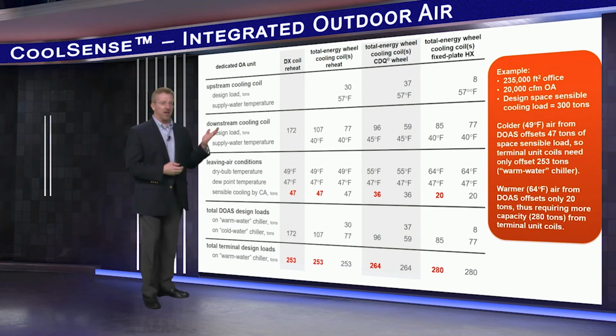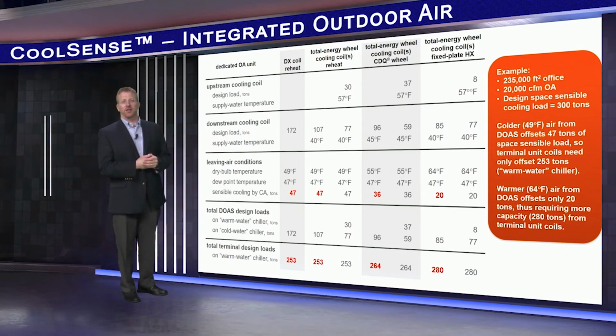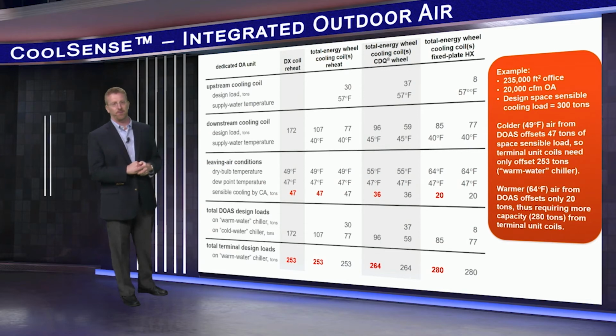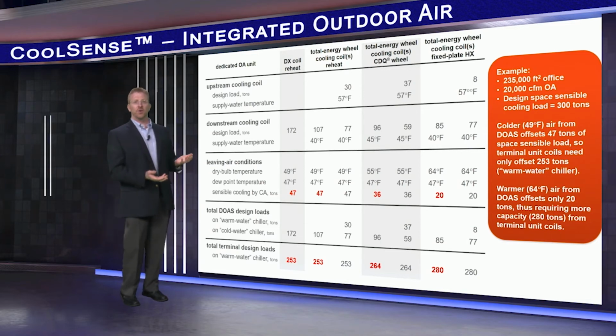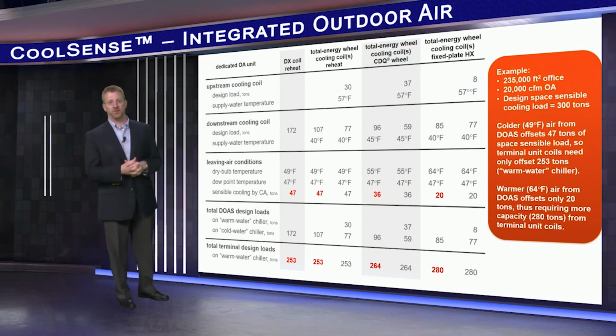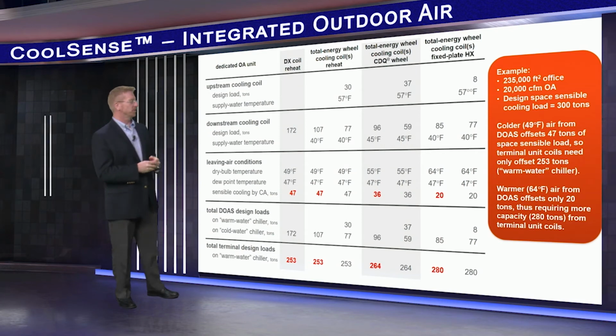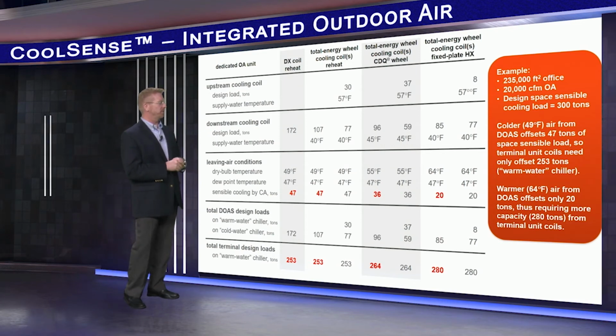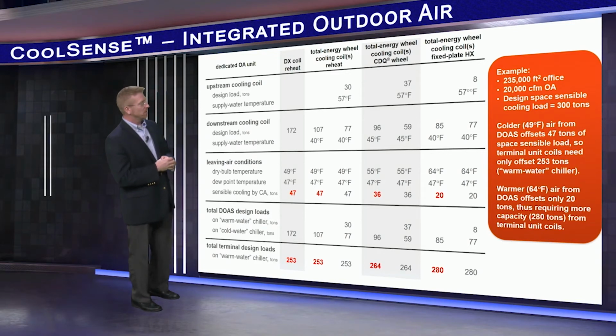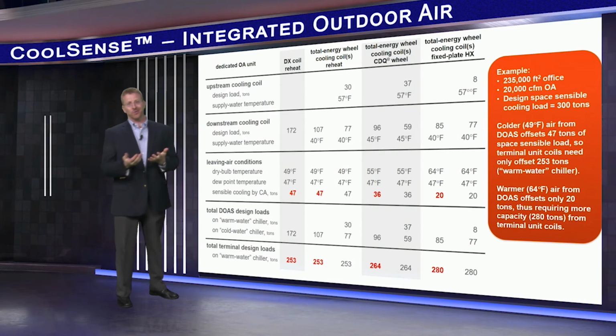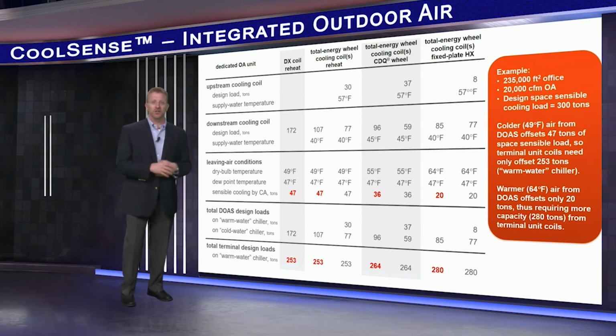First, in the far left column, the DX dedicated outdoor air unit with the hot gas reheat, certainly the least expensive of all options, shown here without any exhaust air heat recovery. Moving to the next column, the chilled water DOAS unit with total energy wheel. It's the simplest of the water-cooled configuration designs with the smallest footprint. It also delivers the coldest air at 49 degrees compared to 55 degrees or 64 degrees with the other 2 configurations. This allows the zone level terminals to be downsized the most, but some designers are concerned about downstream duct insulation or condensation issues with this cold of air.